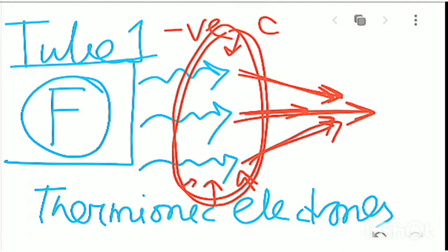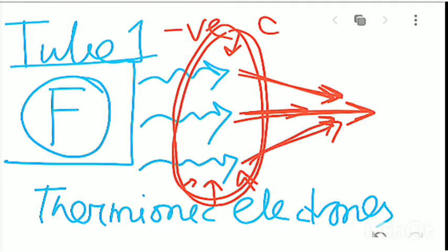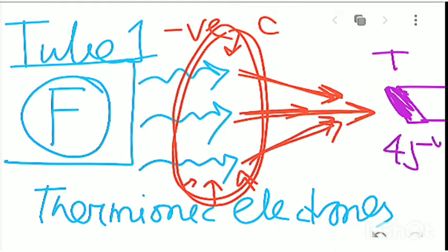and in front of this we keep the strong copper block, and in front of this at a 45-degree angle we keep a very specific kind of material which has a high melting point and higher atomic weight, like molybdenum, like tungsten. This target T is kept at an angle of 45 degrees.